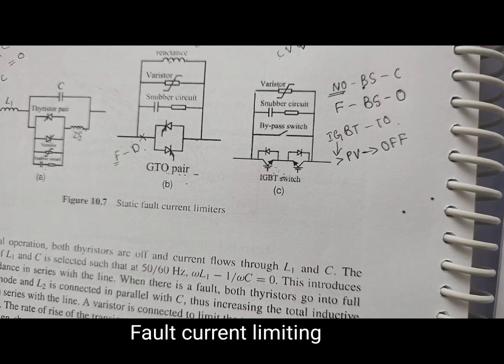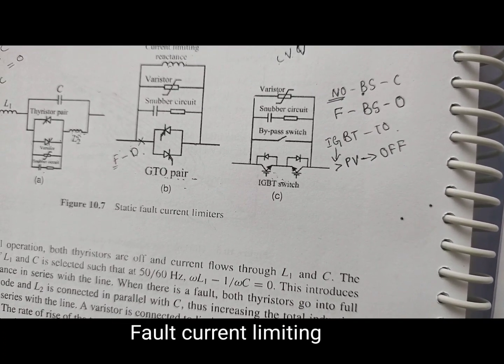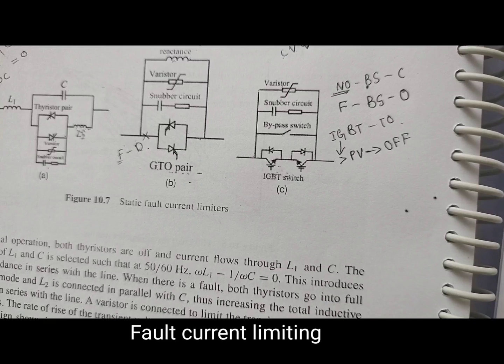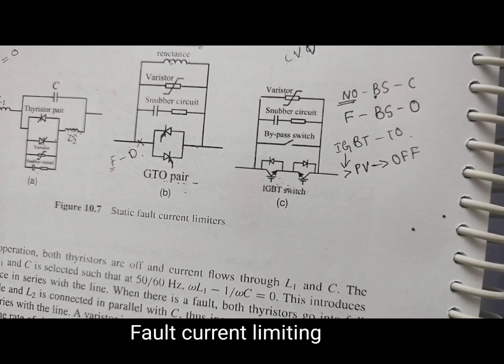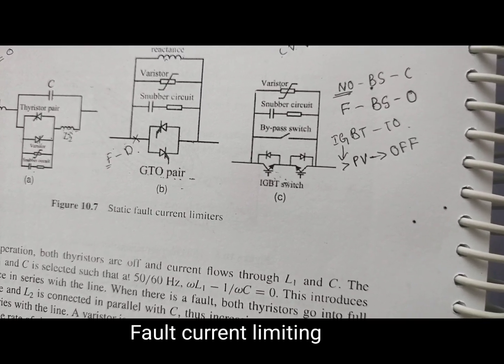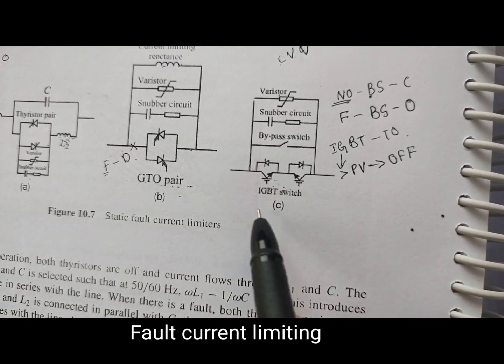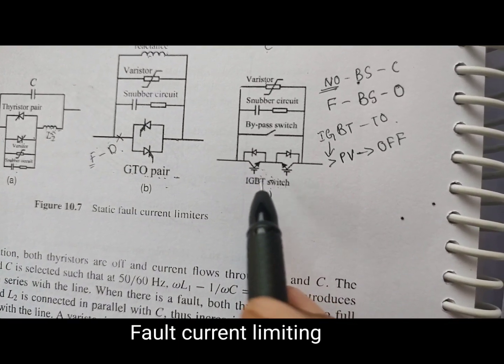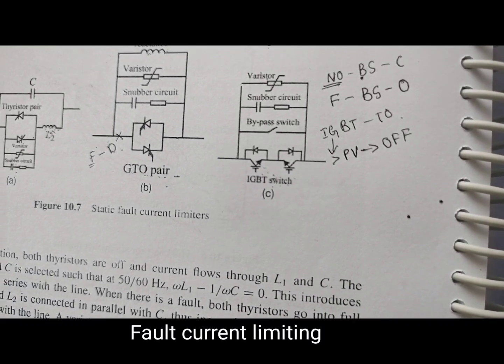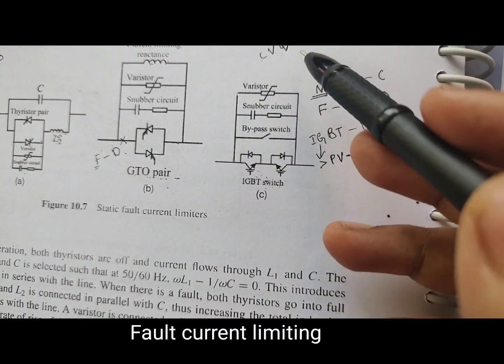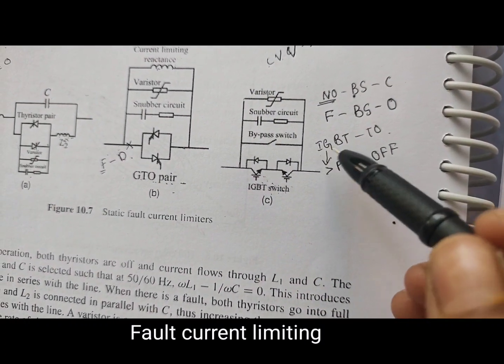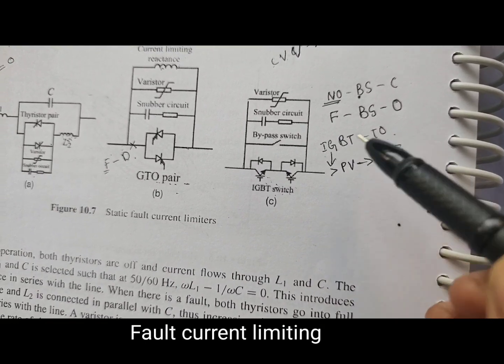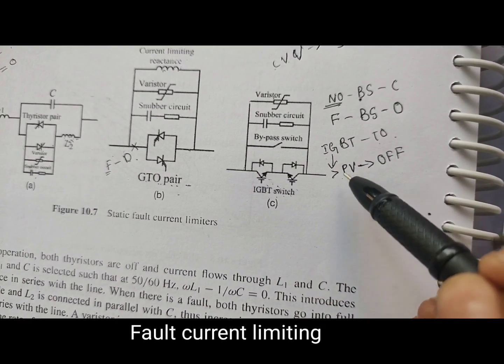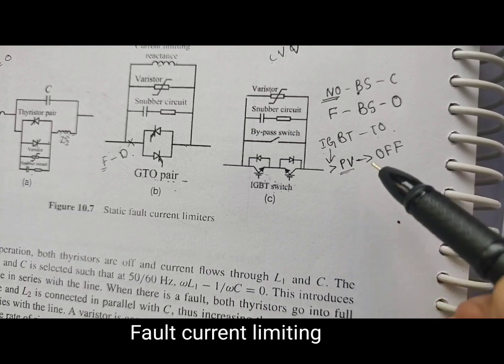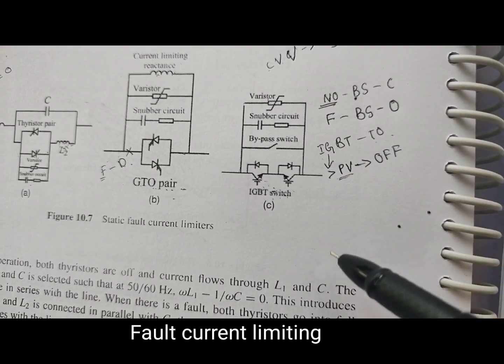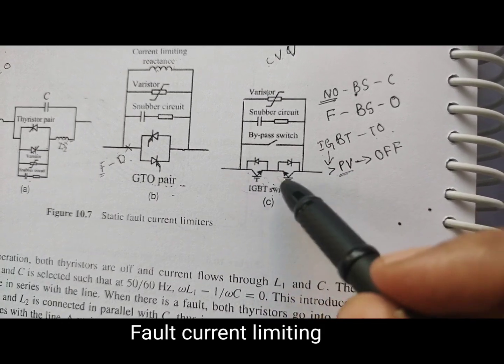When the current reaches a minimum value and is decreasing, the IGBT is automatically turned on again. In this way the fault current is maintained below a maximum value. Once the current starts decreasing and comes back to the normal value, the IGBT will be switched on.